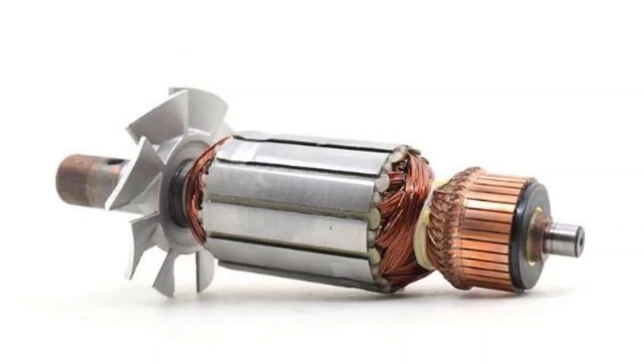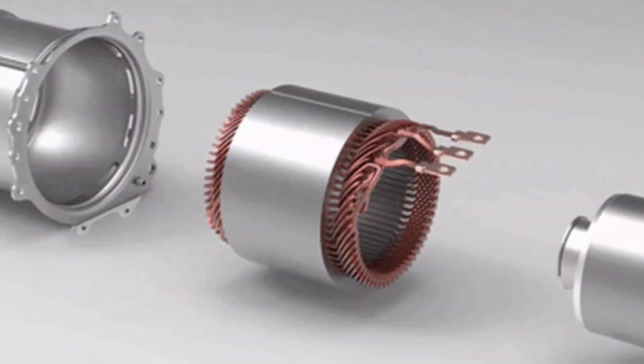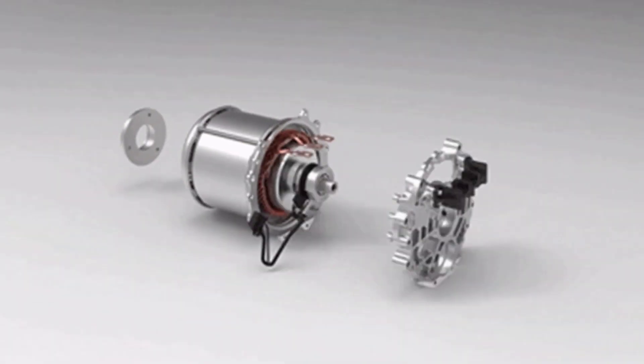Then there is the rotor. A rotor is a central component of a motor that is fixed to the shaft. The most common type of rotor used in an AC motor is the squirrel cage rotor. A squirrel cage rotor is cylindrical and is made by stacking thin steel laminations. Instead of inserting coils of wire between the slots, conductor bars are die cast into the evenly spaced slots around the cylinder. Once die casted, they are electrically and mechanically connected to the end rings.